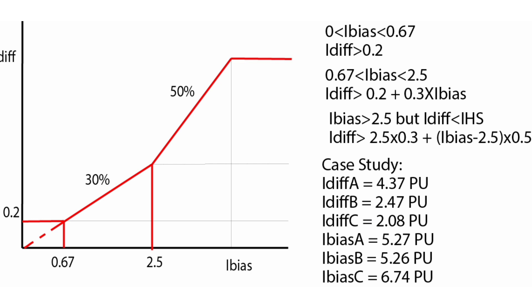For the tripping region: in the first region, up to a bias current of 0.67 per unit, the differential current must be greater than 0.2 per unit for the relay to send a trip signal. For bias current greater than 0.67 and up to 2.5 per unit, the differential current must be greater than 0.2 plus 0.3 times the bias current for the relay to give a trip signal.